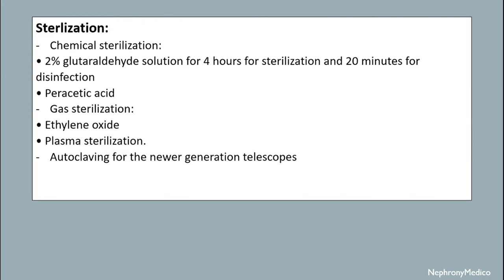Sterilization. There may be chemical sterilization, gas sterilization, or autoclaving for the newer generation telescopes. In chemical sterilization, 2% glutaraldehyde solution is used for 4 hours for sterilization and 20 minutes for disinfection; peracetic acid may also be used. In gas sterilization, ethylene oxide and plasma sterilization is used.